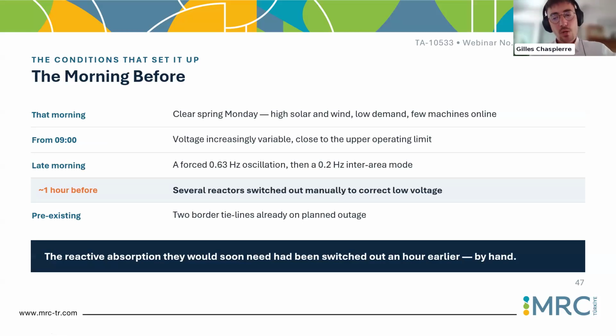So that was really also an important message of the report. It's a bit of bad luck, if we can say, because in this specific morning, first, okay, it was low load condition, clear sky, meaning a few machines online, meaning a few assets able to control the voltage. The grid is lightly loaded. A grid has never been designed to be lightly loaded. If you build transmission corridors, you expect them to be loaded, otherwise you are over-investing. But with the energy transition, more and more distributed generation, mainly rooftop PV, we are facing situations where the grid is no longer loaded at all, leading to over-voltage because a lightly loaded grid is capacitive.